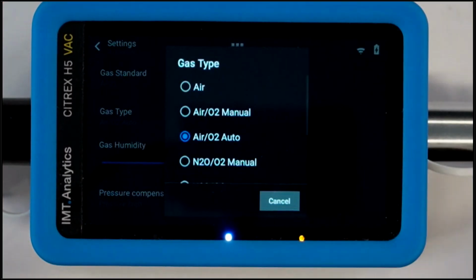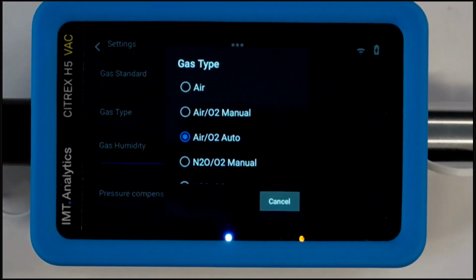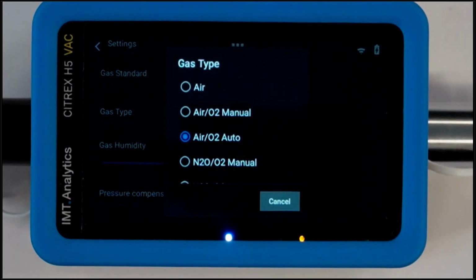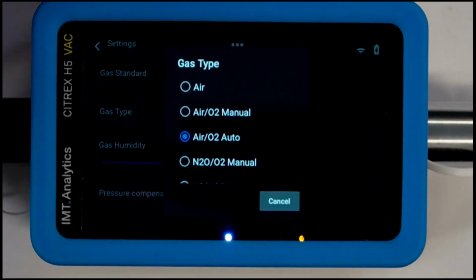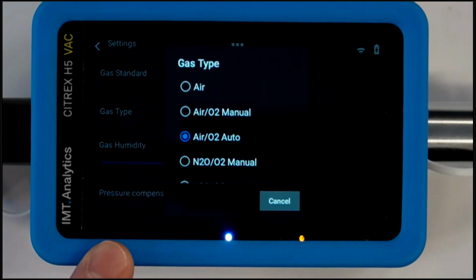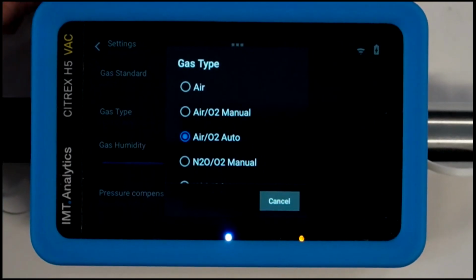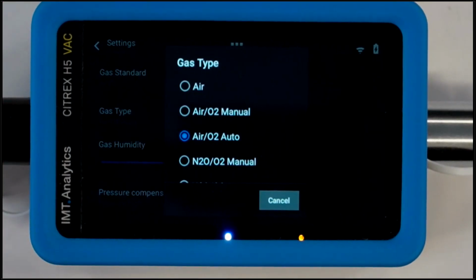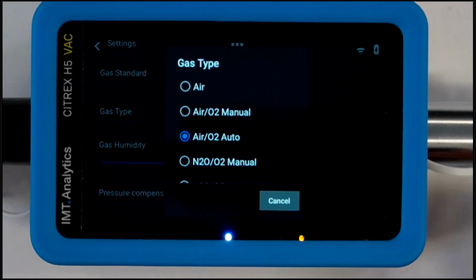Here you'll see that we can select air, Air O2 manual, Air O2 auto, and several others. In most cases, Air O2 auto works best. It uses the onboard O2 sensor to measure how much oxygen we're delivering. So as we make changes to our ventilator and deliver something besides just air, it will automatically detect that and compensate for it. If for some reason you don't have the O2 sensor, you can switch to air or air and O2 manual and put the data in that way. For now, we're going to leave it on Air O2 auto.